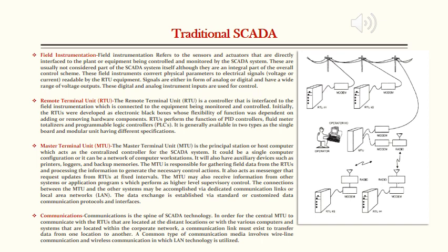Master Terminal Unit: the MTU is a principal station or host computer that acts as a centralized controller for the SCADA system. It could be a single computer configuration or a network of computer workstations, and will also have auxiliary devices such as printers, loggers, and backup memories. The MTU is responsible for gathering field data from the RTUs and processing the information to generate necessary control actions. It also acts as a messenger that requests updates from RTUs at fixed intervals.